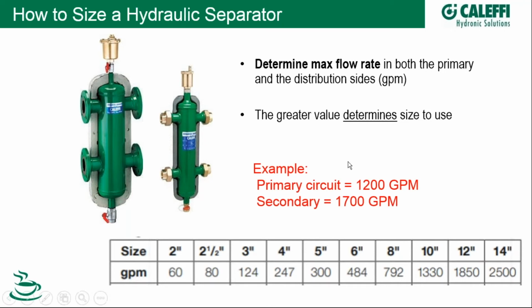So for example, if our primary design flow rate is 1,200 gallons per minute and secondary 1,700 gallons per minute, which isn't untypical, having your primary lower than your secondary in application, then the secondary circuit is the criteria, and we can see we would have to choose a 12-inch pipe diameter hydraulic separator to accommodate that 1,700 properly. Okay, so pretty straightforward.